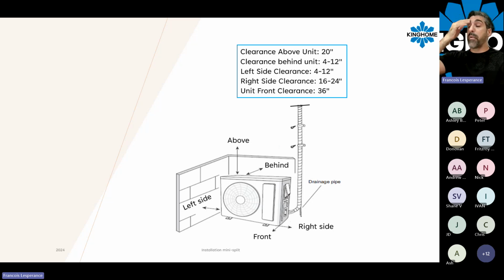And above the unit, we ask to have a minimum of 20 inches for maintenance purposes. On the ductless systems, we have to remove the top panel to gain access to do good maintenance or troubleshooting, whatever. So 20 inches above the unit is a bare minimum.